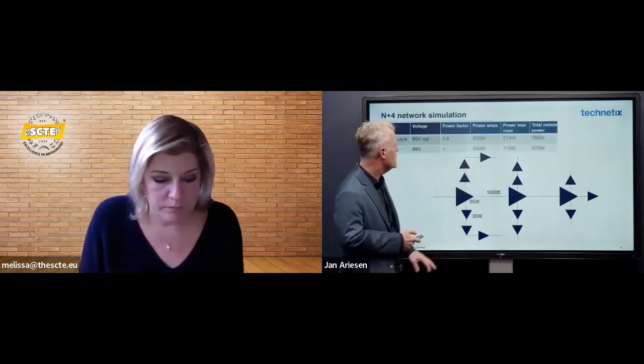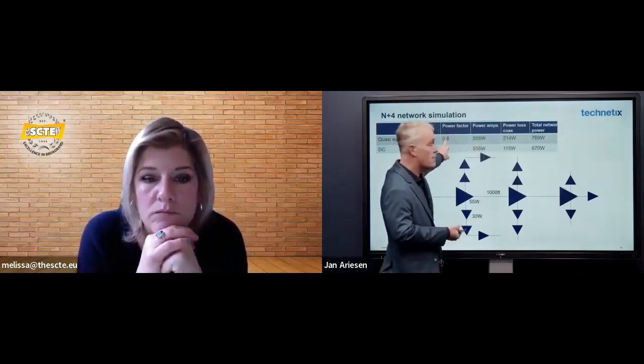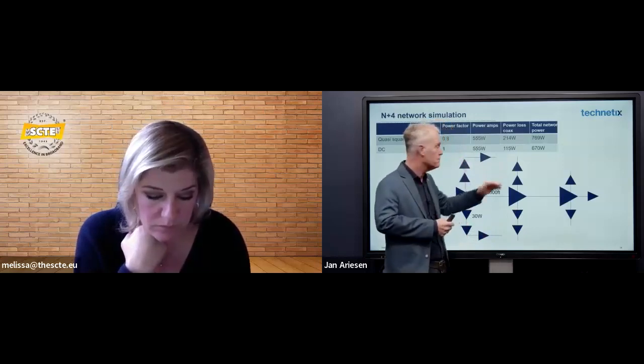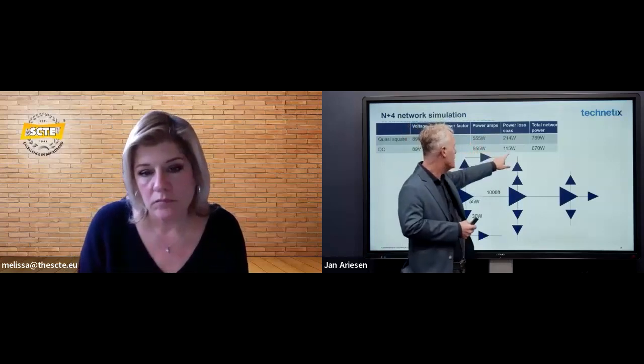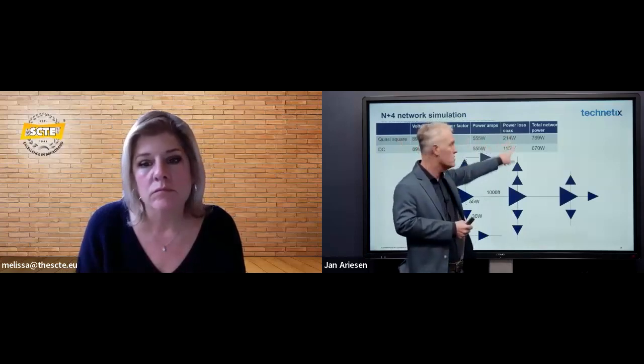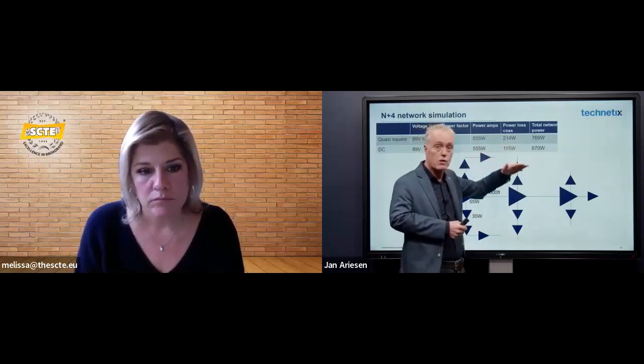Calculated it, tested it. So to give you an idea, if I look at the same network, just a different way of feeding it, the amplifiers in both cases are 550 watts. The power factor this time was about 0.8, and with DC I have a power factor of 1, because there is no mismatch between capacitive and inductive loading on a DC. So that's always a 1. Therefore, you see that a big difference is in the cable loss. The cable loss in this case with quasi-square is 214 watts, and on DC it is 115 watts. And that's just because the amplitude is lower and my power factor is 1.